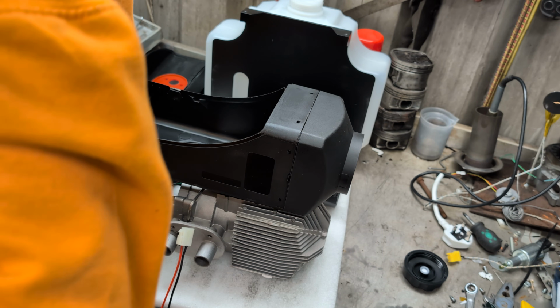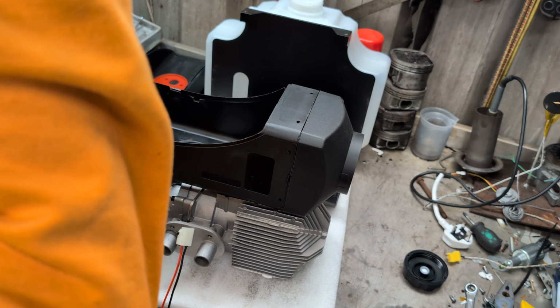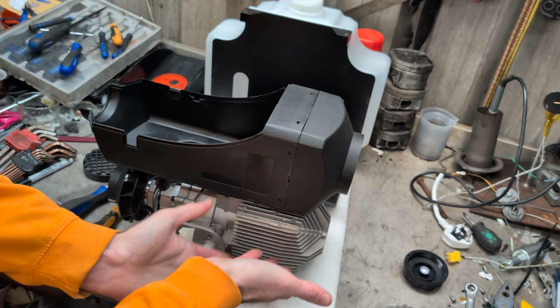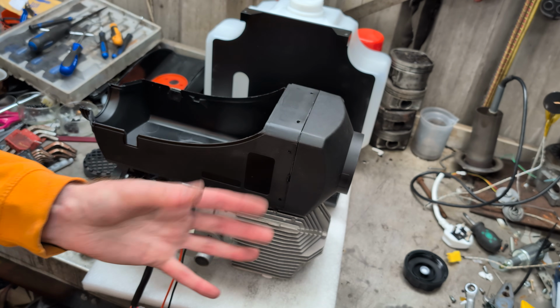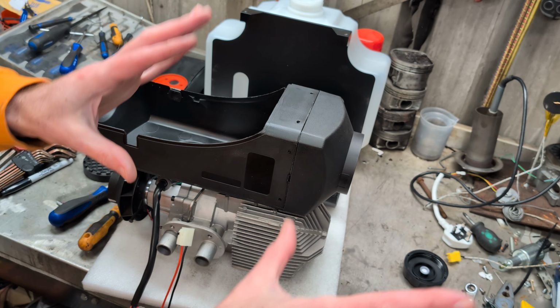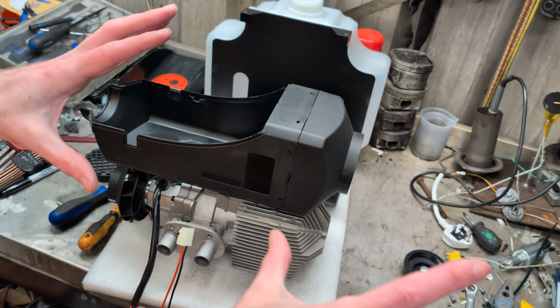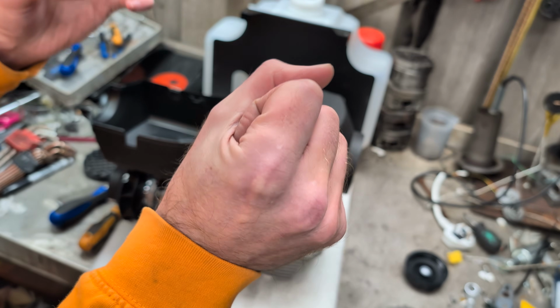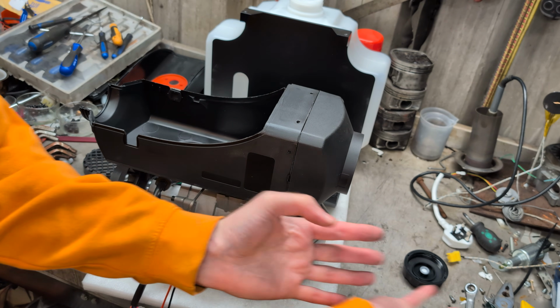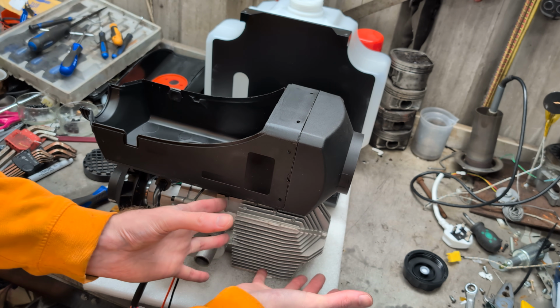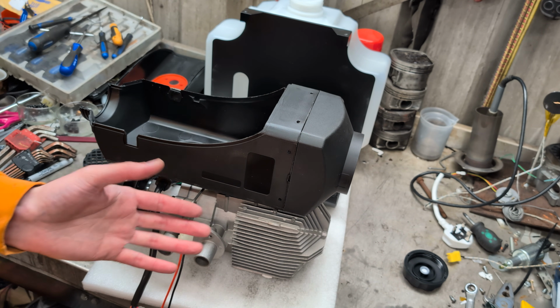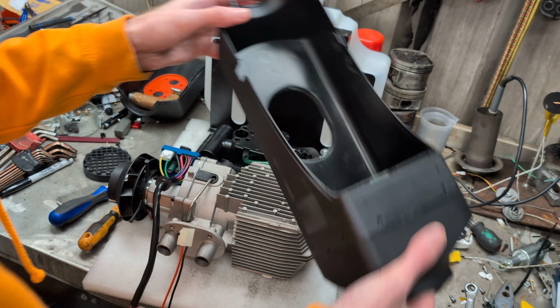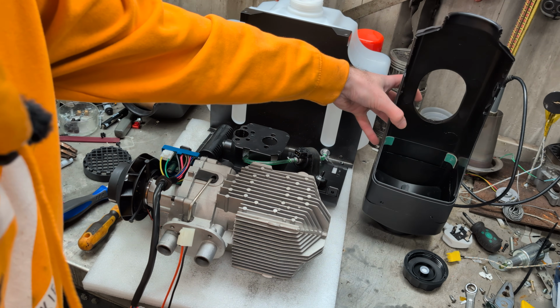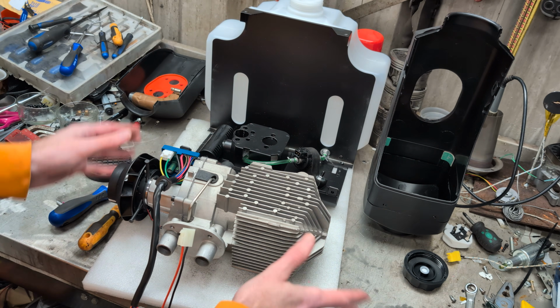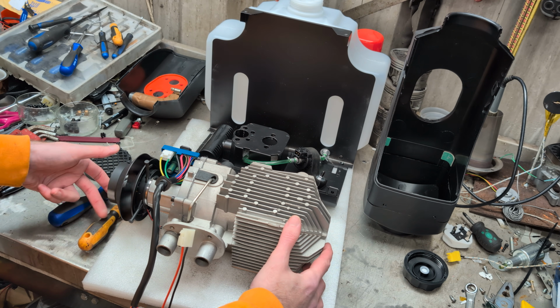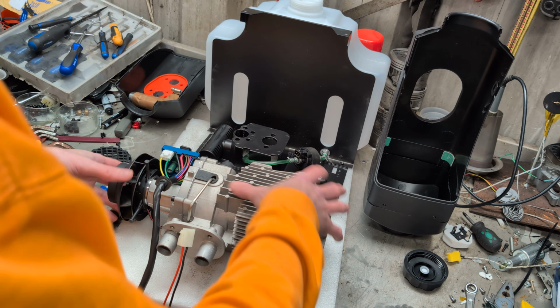Oh God, we've done videos on this, I'm going off on a rant and a tangent here. There's no way you can get 8 kilowatt out of a 4 kilowatt body, you just can't, not with the stock controllers. You could probably get it if you built your own controller and got the fans spinning fast enough, but normally you just can't, the heat exchanger is too small to put the heat out, and you're just wasting heat out of the exhaust pretending to be an 8 kilowatt. Anyway, rant and tangent over. They're all 4s this size, perfectly fine, adequate 4s, just not 8s. Don't be calling them 8 kilowatts when they're not.